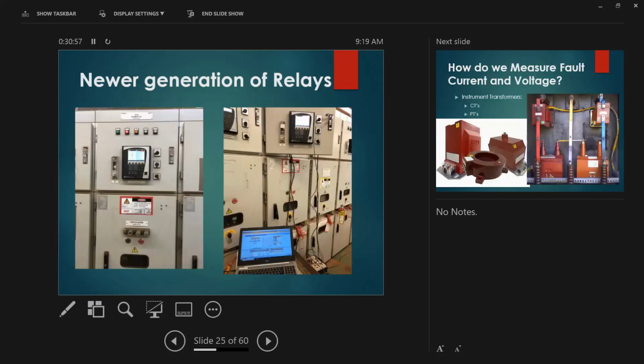But in our time, that's the new generation of relay. Those many boxes or relays on the door mounted, now it's only one. All the functions need to be activated and it will provide you the protection that you want. So it saves space in terms of installation, and also it gives you more flexibility. And also in wiring, you have a couple of wirings at the back compared to the old generation of relays.